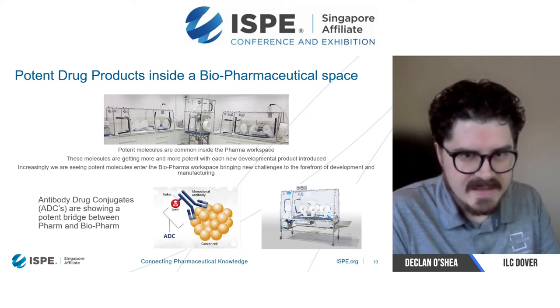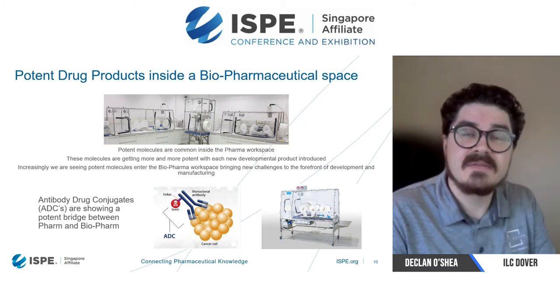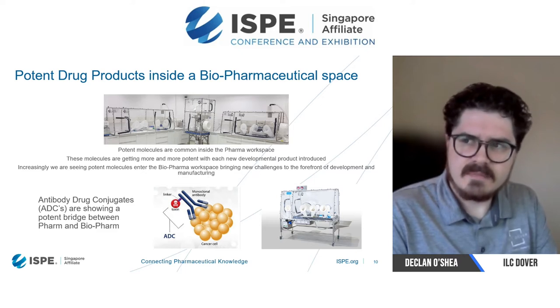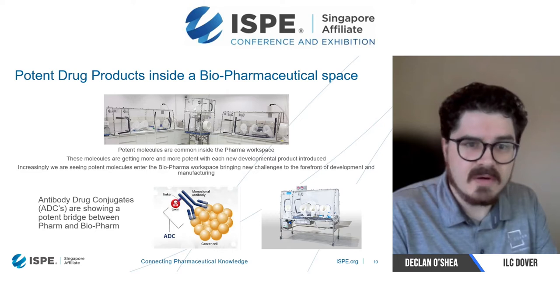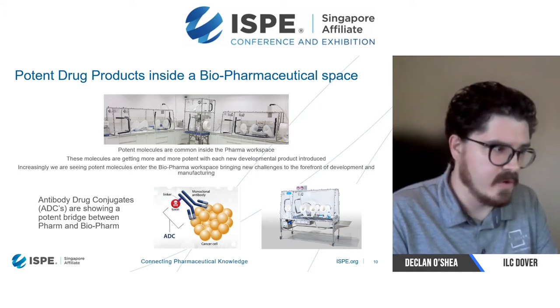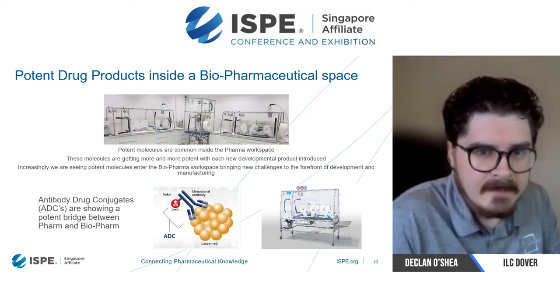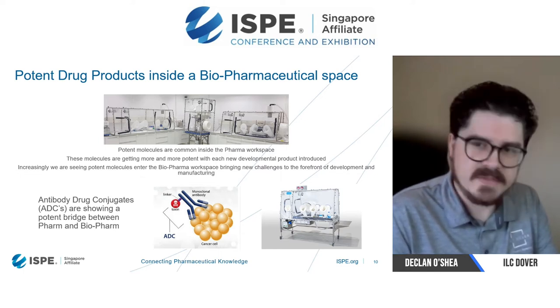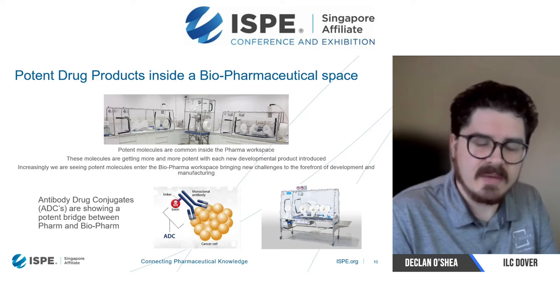What we're seeing at the moment is a large increase in higher-potency pharmaceutical substances within the pharma space. We've seen this growing over the past 10 years or so. Now, instead of seeing 10-microgram substances, we're seeing nanogram substances running down to some of the most potent things, like antibody drug conjugates, for instance. A lot of these are looking down to 10 nanograms, down to one nanogram OEL potency levels, which are increasingly difficult to contain and to pass actual containment tests on. But the potency of these molecules is not impossible — we have proven it. And we are seeing this translate to the biopharmaceutical space as well.